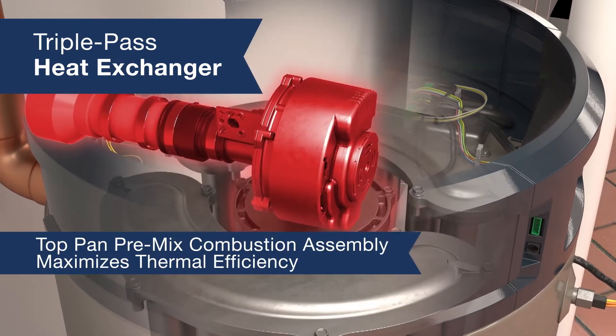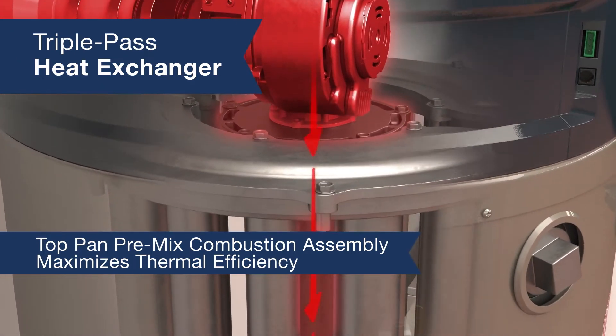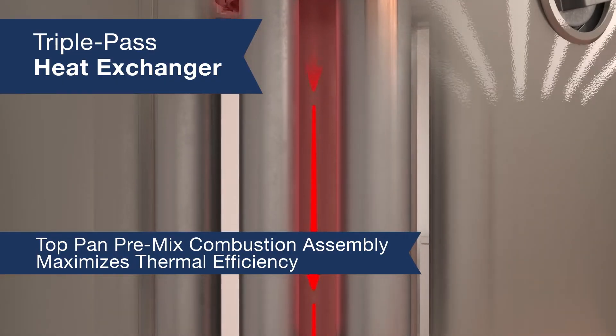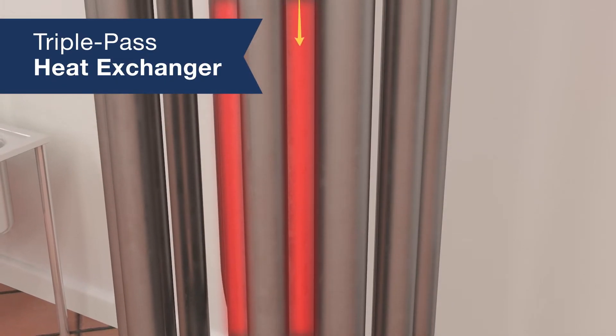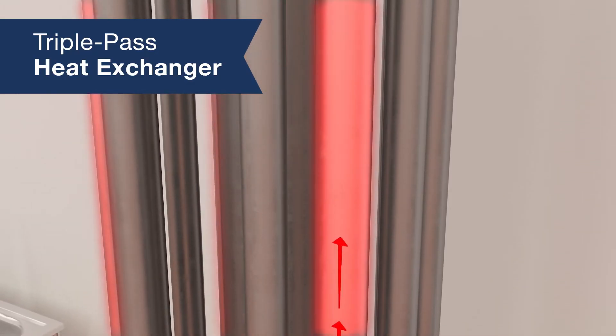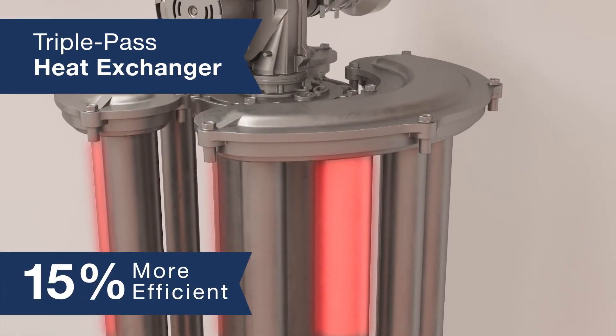The pre-mix combustion assembly is located at the top pan, which efficiently mixes gas and oxygen to provide maximum thermal heat transfer in the heat exchanger. The majority — 80% of the heat transfer — occurs in the first pass of the heat exchanger, then the flue gases transition to the secondary tubes. At this point the system becomes 15% more efficient.